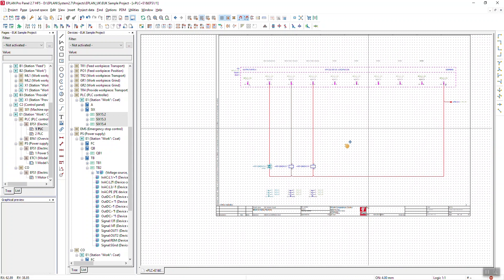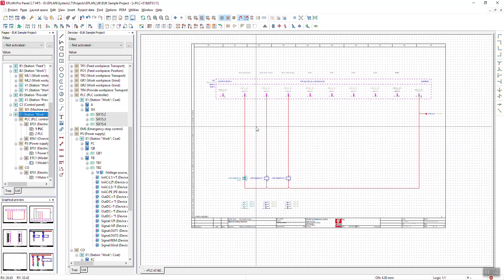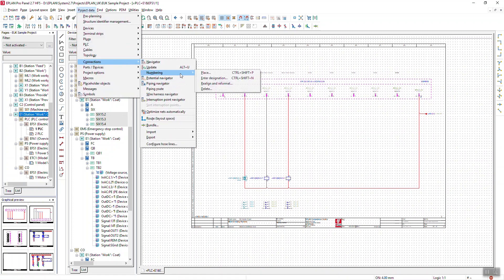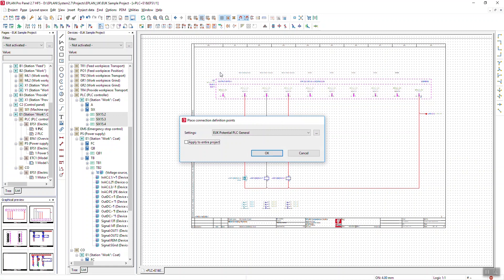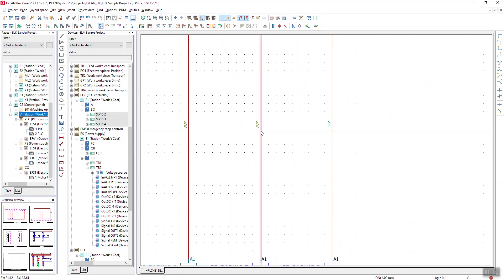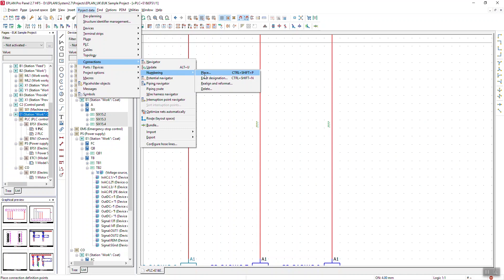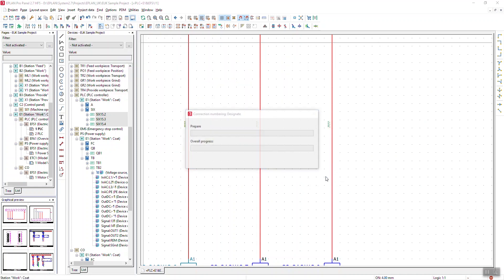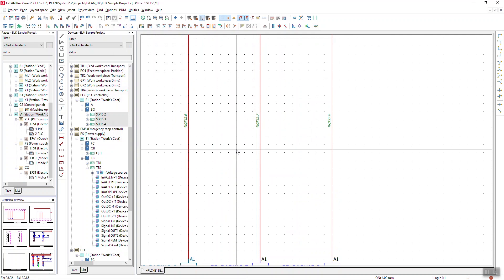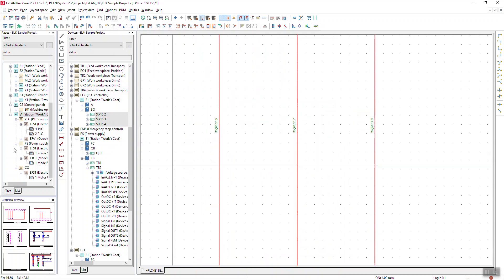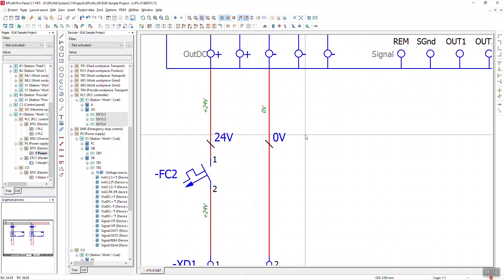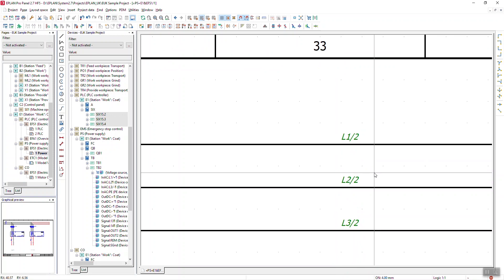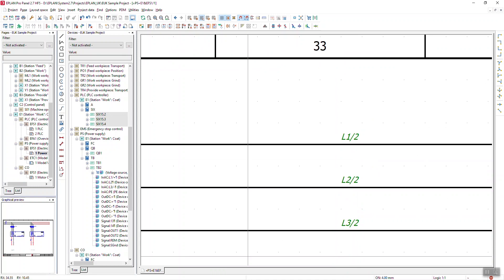So that's device numbering done. For wire numbering, it gets into a whole bigger area. I go to Project Data > Connections > Numbering, place the items down and you can see the markers appear. Again, Project Data > Connections > Numbering > Enter Designation. By pressing OK, I can number either via a PLC set, via L1 and L2, or via 24V and 0V — depending on what I want. L1, L2, and L3 are available too, making automated numbering very simple and easy. Thank you for your time.